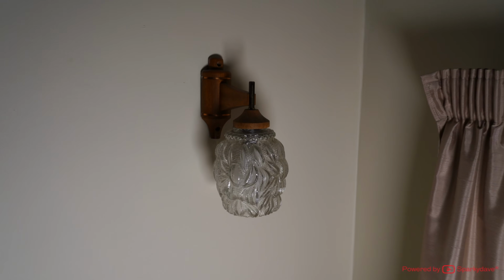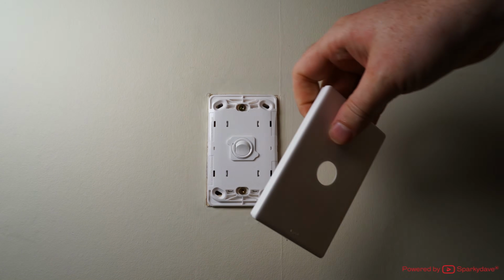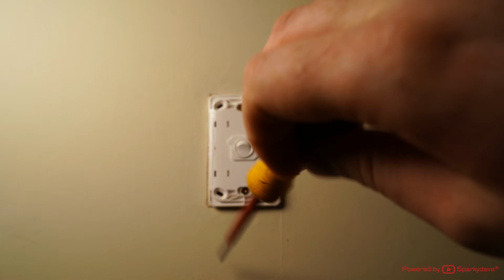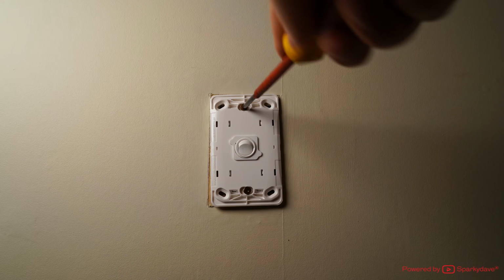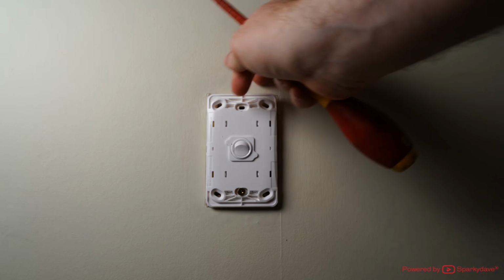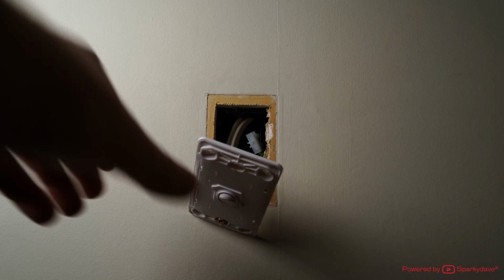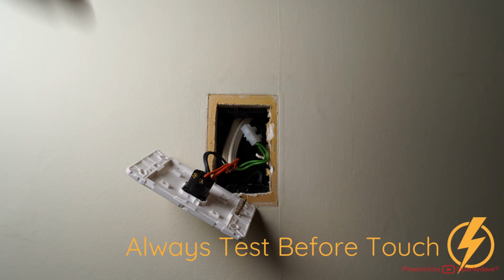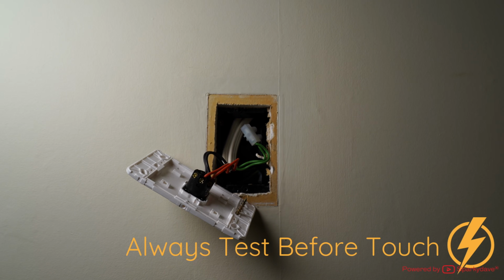The wall switch should no longer operate the associated light fitting if the correct circuit breaker is isolated. Remove the light switch from the wall, ensuring care is taken not to touch the terminals until verification is made that the fitting is not live. Always test before touch with any electrical fitting or terminal.